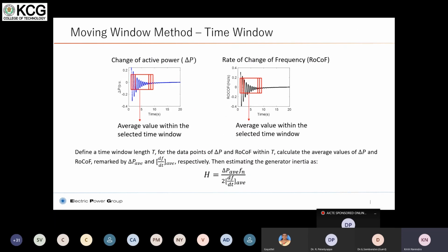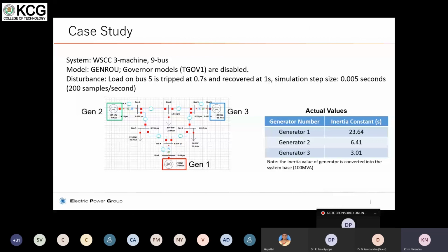On the left hand side, there is the average value we have found for each selected time window, which is a movable window, when there is a change in delta P that happens when the disturbance happens. Similarly, the ROCOF is another quantity that we evaluate when a disturbance happens, with the same time window. The same time window is applicable for both. Now, defining a time window of length T, H of the system is calculated like this. We have done the study for the Western system interconnection with the 3-machine 9-bus system. It's a Western connected system, which is a reduced system, which has 3 generators and some transmission lines and loads and so on. You can see that the inertia constants of the generators are 23.64, 6.41, and 3.01 seconds respectively, based on 100 MVA.